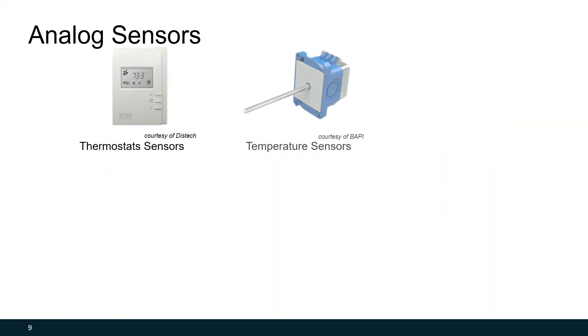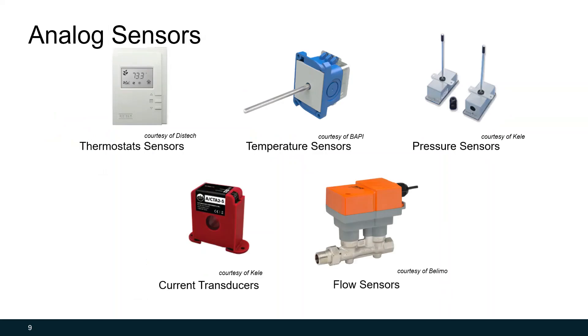There are many types of analog sensors. We've already discussed thermostats and temperature sensors, but you can also have pressure sensors, current transducers, and flow sensors. There's many types. A good example of the difference between an analog sensor and a binary sensor would be the current transducer. A current switch detects whether or not there's electricity flowing through a wire, but a current transducer is trying to tell how much current, how many amps are flowing through that wire.